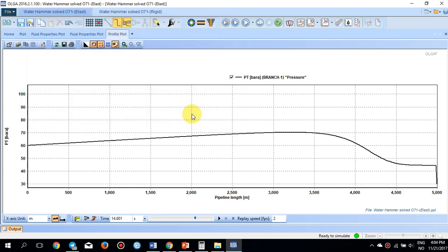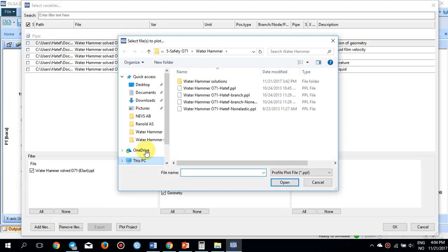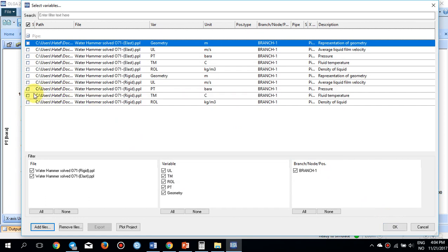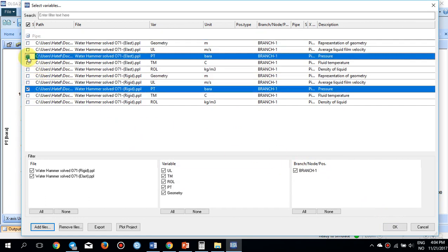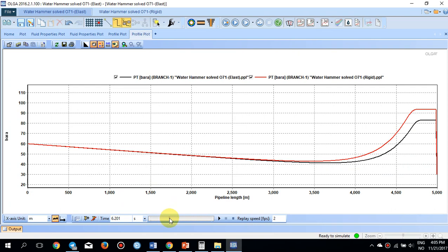Once the rigid wall simulation is also finished, both cases are compared on the same plot — PT for both elastic and rigid cases. The red curve is the rigid case and the black curve is the elastic case. The pressure peak in the rigid case is much higher than in the elastic case, and the elastic case shows clearly dampened pressure waves.